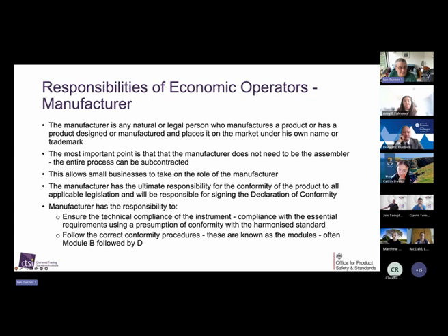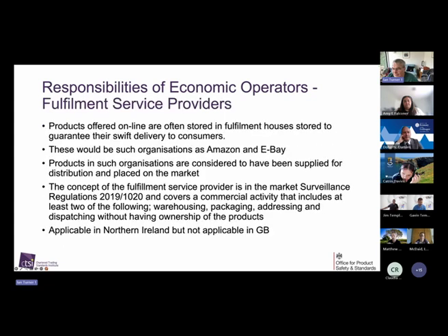And just to emphasize the point, if we go back to this one here, although I go to my friendly jolly butcher in Belfast who's bought it off eBay, and you stick a kilo on it and it weighs a kilo, it hasn't had any of the conformity assessment procedures. And that's the point. Quite often, I've played with these things forever, these 30 to 50 quid scales, and it's the drift. If you leave 3 kilos on it for 20 minutes, it then gives you a completely different weight. And it is temperature compensation, things like that. Even funny basic stuff. One I bought once, 35 quid delivered, had a GPSR issue, amongst other things. You could run your finger along the edge of the pan or lift the pan off and it cut your finger because the metal was so sharp. It was just a silly thing that you never think of, do you? You've got to be able to stick stuff on it without hurting yourself.